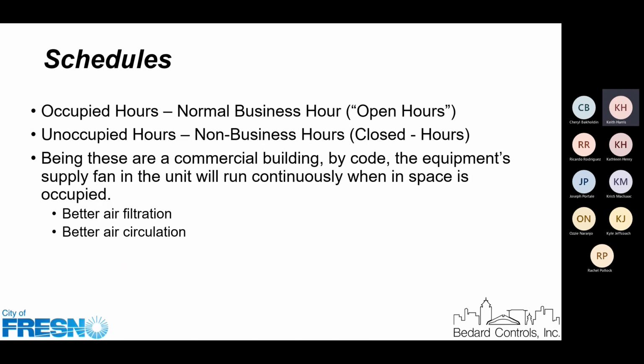One thing I mentioned earlier is because they are commercial buildings by code, the supply fan, the fan that moves the air around in the space, is supposed to run continuously. That's probably different than what you're experiencing currently, because most of the thermostats we've run into are more of a residential style, meaning they only run the supply fan when they're in call, or they're calling for heating or cooling. Because this is a commercial space, because the code requires that we run the fan continuously, we run it when it's occupied. So the fan will be running even though there isn't a call for heating or cooling, and that's to get better circulation and better filtration of the air. It's not a bad idea in our era of COVID, but it is probably a difference from how the building's currently being operated.